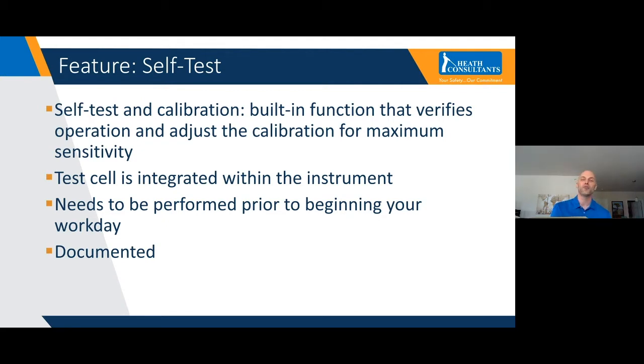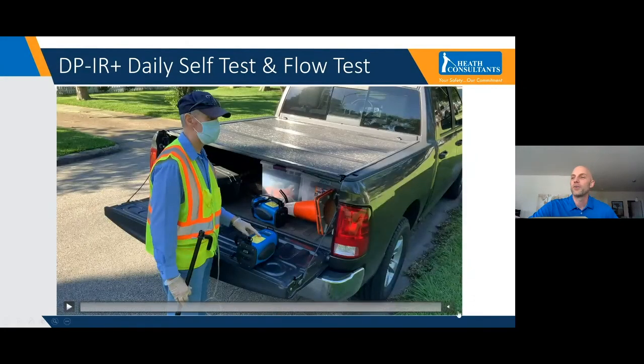Inside the instrument, there's a little reference cell, or calibration cell, with a known quantity of methane, and it's on a little rocker arm. If you remember, I said there's a chamber inside with light shining from one side to the other. Once you start the self-test, it puts that rocker arm into the infrared light path, and then it adjusts itself. Again, we recommend doing this once a day. I'm going to show you a video of this.